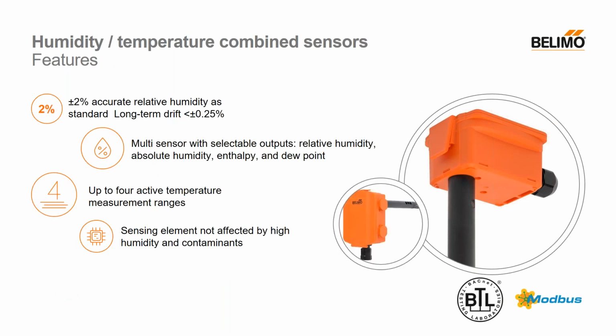When it comes to humidity sensors, we're first going to talk about our duct mount humidity sensors. Again, as I mentioned earlier, they're all plus or minus 2% accuracy. They're going to have different outputs, so you don't need a different sensor for relative or absolute humidity or dew point or enthalpy. All those values are jumper selectable outputs or analog outputs, and they can all be read via BACnet or Modbus. So that is to say, if you address one of these sensors and put them on your network, you can pull up a BACnet object for relative humidity, absolute humidity, dew point, and enthalpy all at the same time. Those that have active outputs have selectable output ranges.